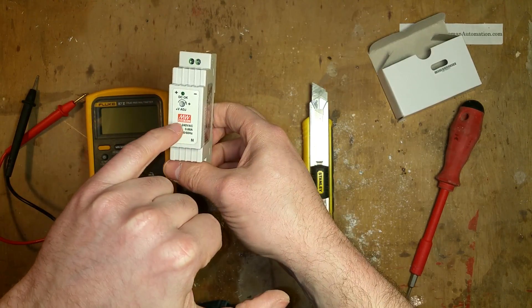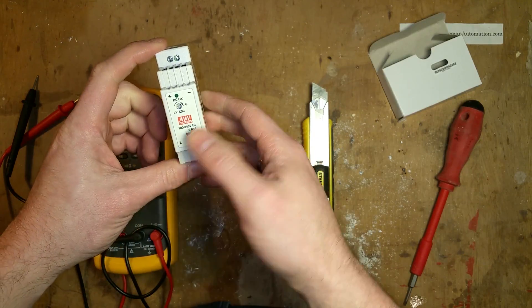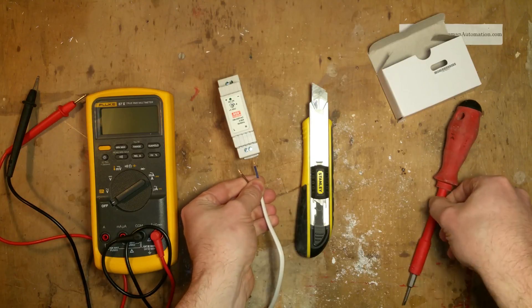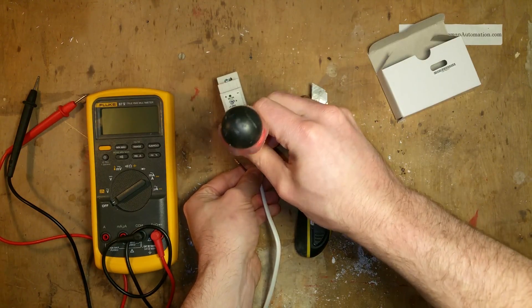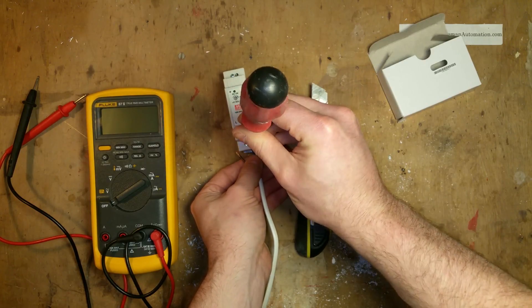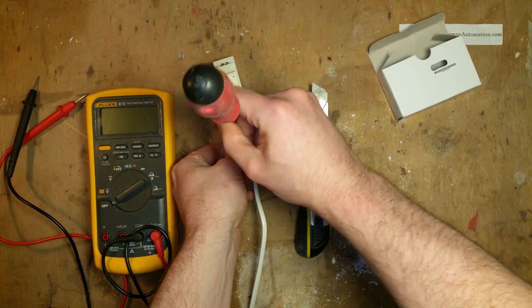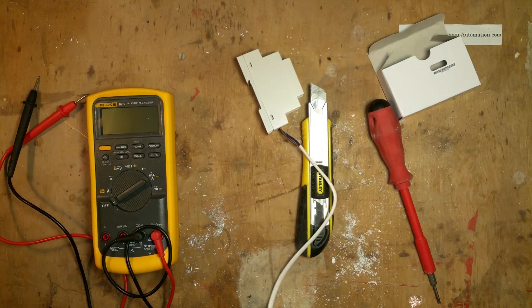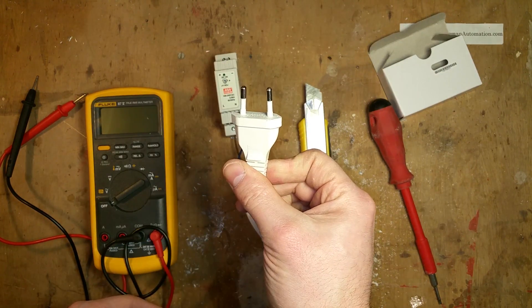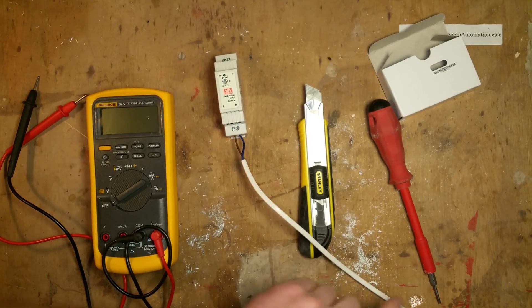Another nice feature I haven't talked about yet is that it is multi-voltage, multi-frequency, so you can use it worldwide. This is a very nice 5 volt power supply to put in your electrical cabinets. Let's connect this to AC. Something also a little confusing is that these terminals come fully closed, fully screwed, which means you have to unscrew the screw before you put the cable in.